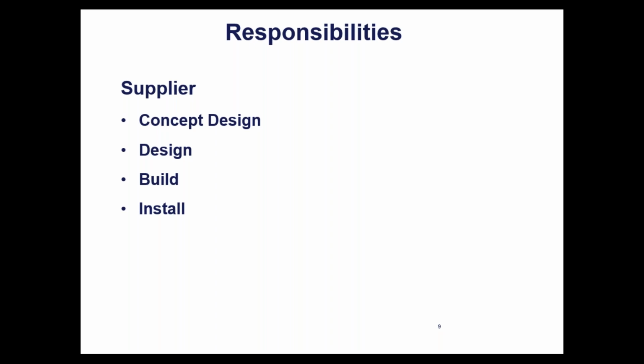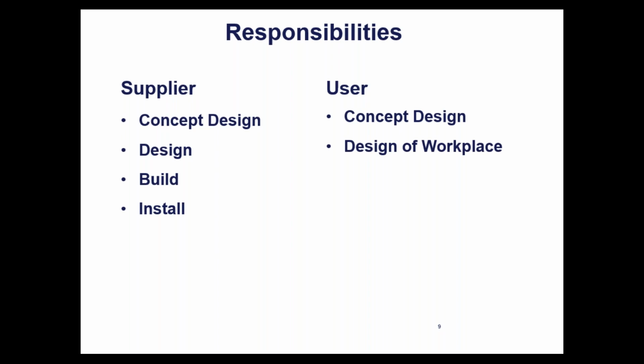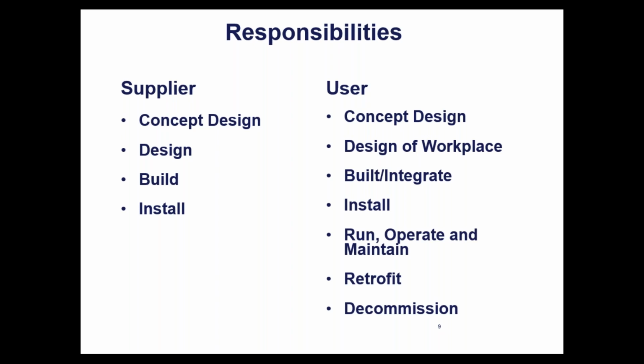Okay. In this case, ANSI B11.0 also makes the user responsible for reassessing the equipment. Besides the concept design stage, the design of the workplace, and build or integrate and install, they also want you to do assessments during the run, operate, and maintain stage of the equipment, basically when you're running production on the equipment. Or if you retrofit the equipment, you're supposed to do another risk assessment. And when you're decommissioning. These are the big differences right now between ANSI and ISO 12100.